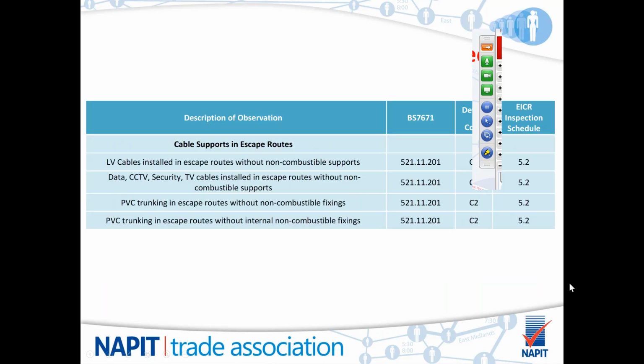Now, something that's come to light in recent years as well is the cable supports in escape routes. If you've got cables going through an escape route, then should there be a fire, those cables still need to be supported so that they don't drop down, impeding people's escape or entry into the building. Should you find cables that aren't supported adequately and can drop down in a fire because they're only held up by plastic tie wraps or a bit of plastic conduit or plastic trunking without adequate support, then you're going to give them a C2.